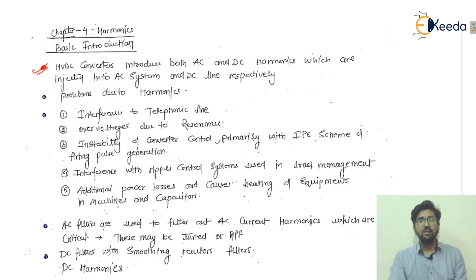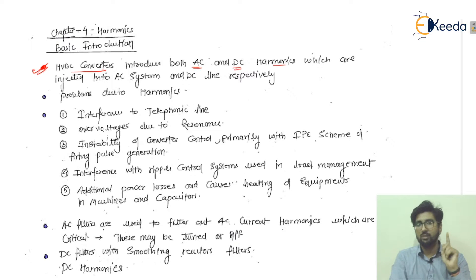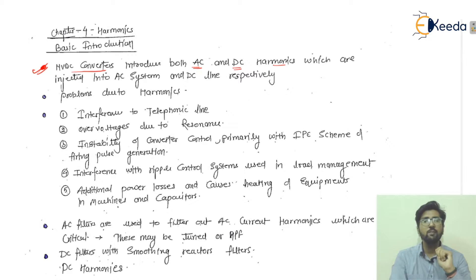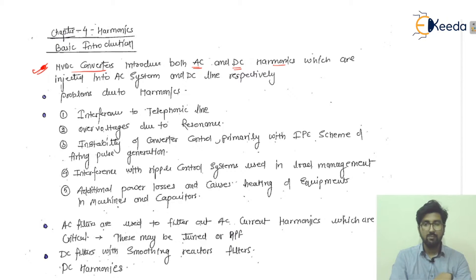The first point is that HVDC converters introduce both AC and DC harmonics. In an HVDC transmission system, from the generating end to the load we are operating with both AC and DC. Between the two converter stations the transmission line carries only DC current and DC voltage, while on either side we have AC fundamental values. On the AC side we have AC harmonics, and on the DC side we have DC harmonics.